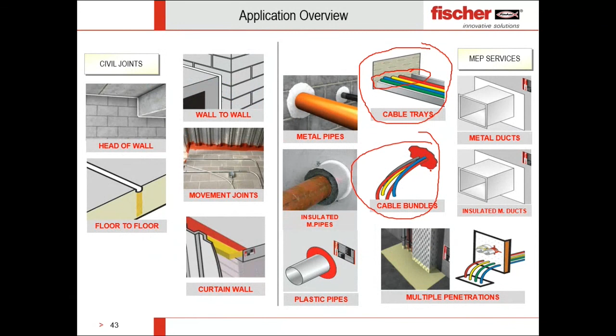We have a solution for all types of MEP, but I'm going to focus today on electricals, for example cable trays and cables. Usually with electricals, the problem is that the cable tray is not always 100% full, it has some gaps. So whatever system we are using has to fill the gap. And when the cable itself burns, because the cable always has plastic around it, the material or sealant has to expand and close that gap, so that fire should not pass even after the cable insulation melts due to high temperature.